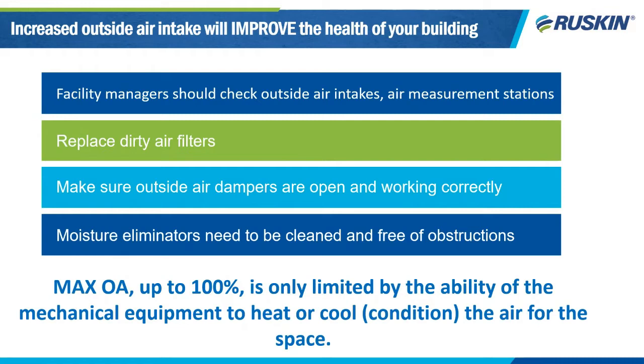The system is generally designed for the hottest day of the year and the coldest day of the year, and when we're not at either one of those extremes, you can bring in more outside air. On a hot day, of course, overventilation can make the temperature in the building less comfortable and result in higher humidity. And on cold days, the building will be too cold. Humidity always needs to be maintained between 40 and 60% for a healthy environment. Air measurement stations can help quantify how much outside air is being introduced or exhausted to keep the building under control and to make sure that nothing less than the required outside air is brought into the building when occupied.